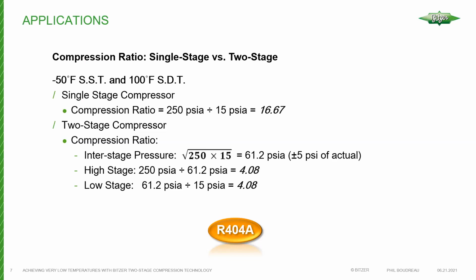Comparing the compression ratios would look something like this. If we have a system, and I'm not sure why I'm changing conditions here, but we're going to use a different example: minus 50 Fahrenheit saturated suction temperature and 100 degree Fahrenheit saturated discharge temperature with a single stage compressor. And keep in mind that when you're calculating compression ratio, this has got to be done using absolute units.